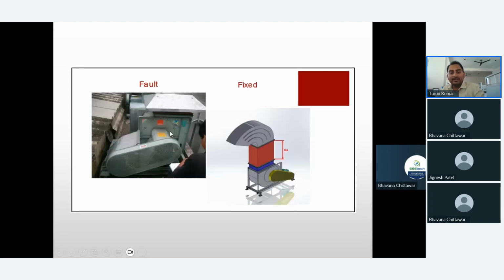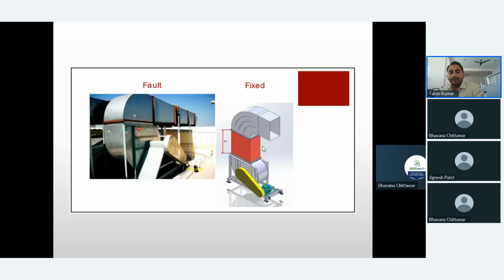You can see here there is a top discharge, and they have put an obstruction above the fan. What they should have done is take a certain length of straight duct, and after that put the bend to get better performance. What will happen here is that back pressure will be generated in the system, your power consumption will become higher, and over a period of time there is a high chance that the bearing will fail.